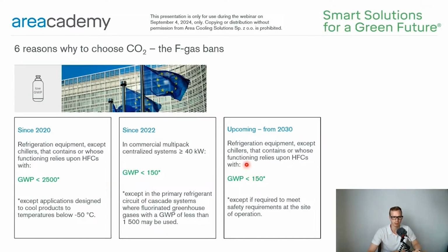The upcoming ban is scheduled for 2030, covering stationary refrigeration devices regardless of capacity and type of application. Only refrigerants with a global warming potential factor of less than 150 will be approved. This means that from 2030, all new refrigeration plants will have to run on natural refrigerants, such as CO2 or on A2L refrigerants. In the official F-gas document, you can find some exceptions for safety requirements, cascade systems, and temperatures below -50 degrees Celsius.